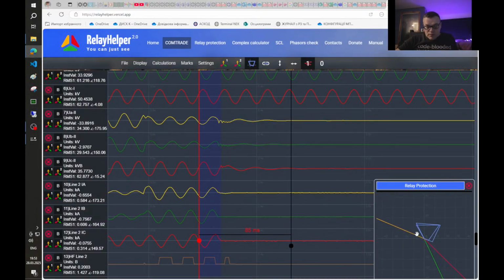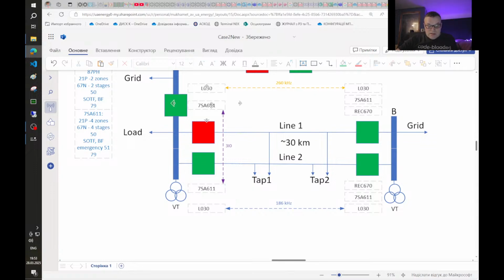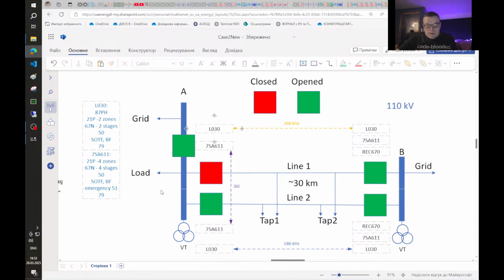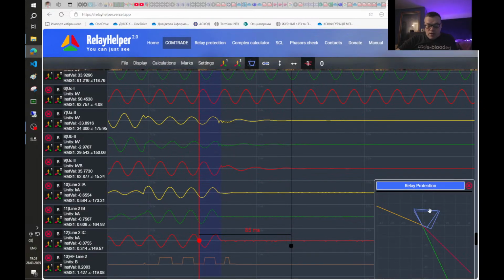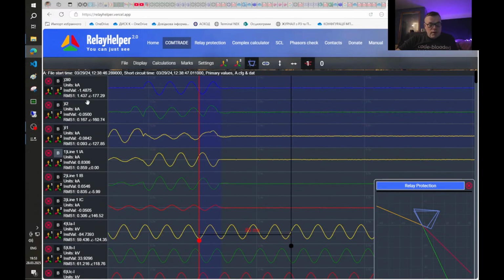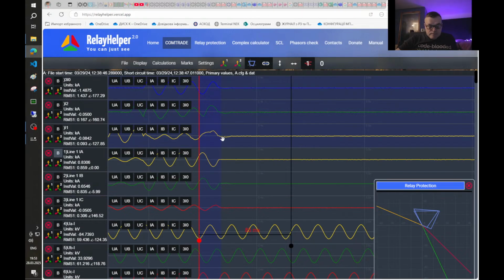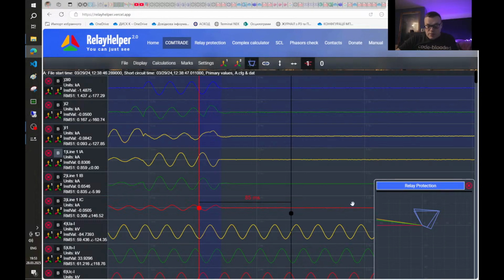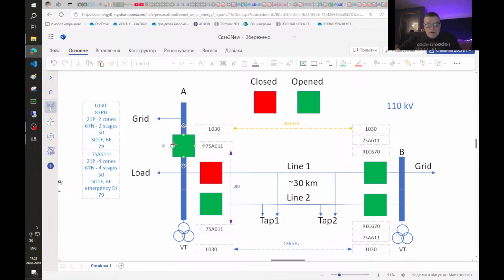It's because here we have only load, not any source. So distance protection from substation A side sees only impedances of the load. For line 1 we have the same settings, so we just need to relink the calculator currents: phase A, phase B, phase C. We see pretty much the same picture. So for distance protection from the substation A side, this fault seemed like an external fault, because only load was connected to substation A.